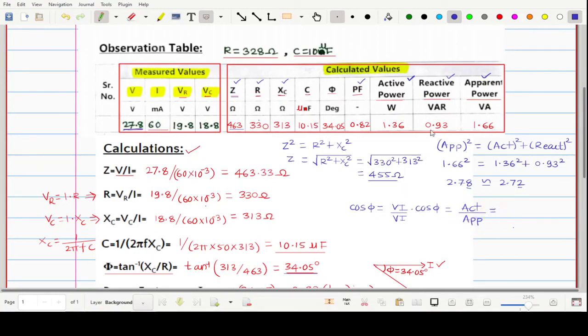We have already calculated these values, so put those values in. Your calculated active power is 1.36, and your apparent power is 1.66. Calculate this — it comes out to be around 0.82. If you compare this value with our measured value, these values are exactly matching, meaning whatever power factor we measured is correct.